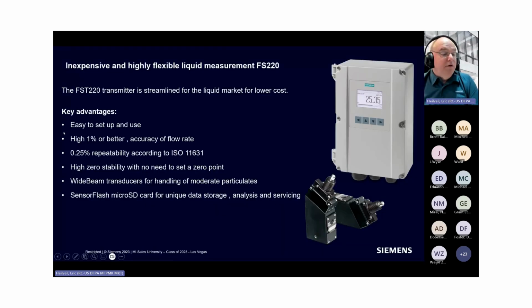All right. So talking a little bit about the 220, I think I've hit most of the high points. They are extremely easy to set up and use. It's a single channel unit. All the information you need to set it up, you can actually derive from the device. So if it hasn't been sized to where you put the transducers, how you mount it on a pipe, all that information comes from the transmitter. The 220 offers a 1% or better accuracy. A lot of that depends on how you mount it. If you do a great job mounting it with a proper run length, then you're fine. If you are not compensating for a bend, you haven't gone into the disturbed flow, the accuracy can degrade. But there are ways to always improve that by modifying the installation.